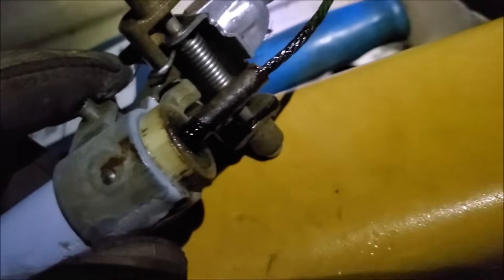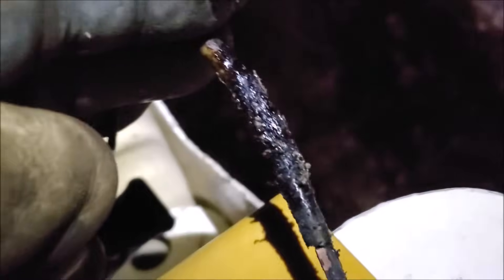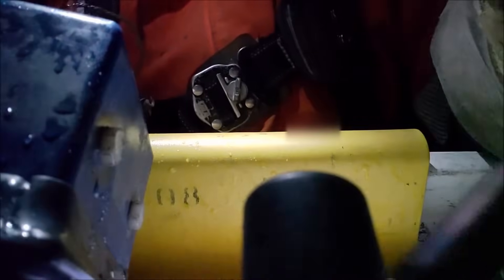You can see the fuse link — it's actually liquid in there right now. She's melting. This is actually an older type door that has the tube attached to the cutout, as you can see. The fuse link screws into the tube.